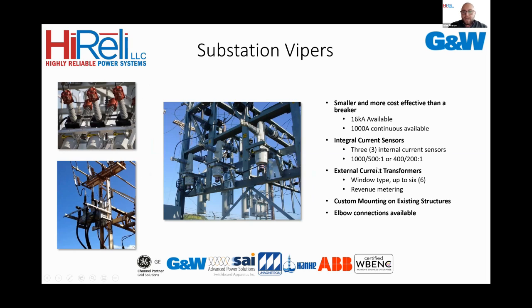The substation Vipers I was talking about, I just want to make sure the 16K ratings and 1,000 amps continuous are available. That allows us to use the reclosers in place of a traditional substation breaker. This is going to be a smaller footprint, more cost effective. We have internal current sensors that are molded within the Vipers, but we can add window CTs external to the Viper, as you see in the top left picture. With the Viper being a dead tank construction, we can slide these window CTs right over, give you a higher accuracy, metering grade sensing.